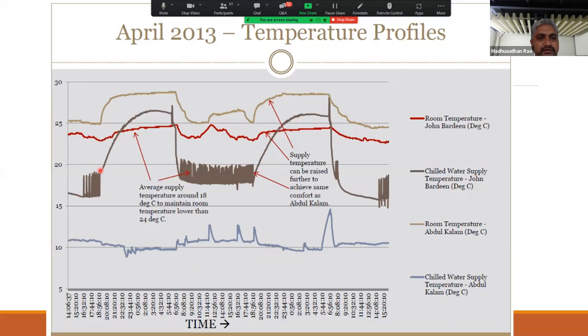And then the same thing, the AHU fan motor is switched off. So you will see an immediate spike in the temperature of that space. The reason is, even if there is no occupancy, there is load. This is April in Hyderabad. The ambient temperature is still higher. So there will be transmission gains.